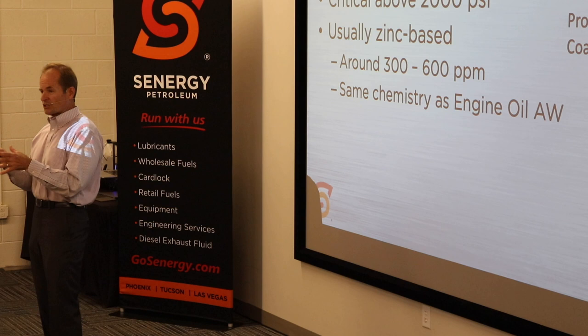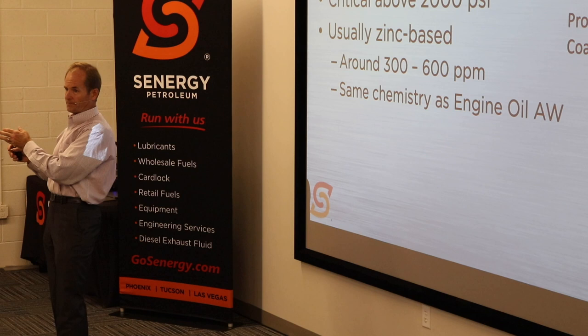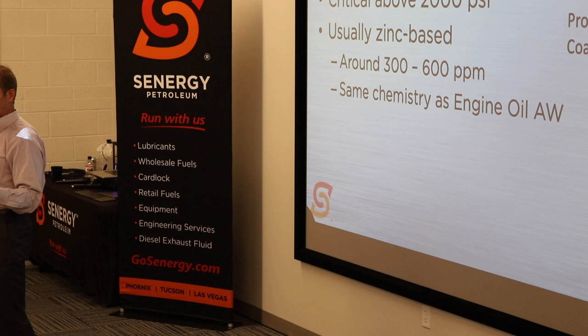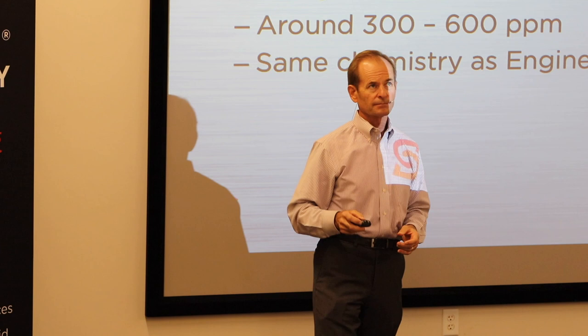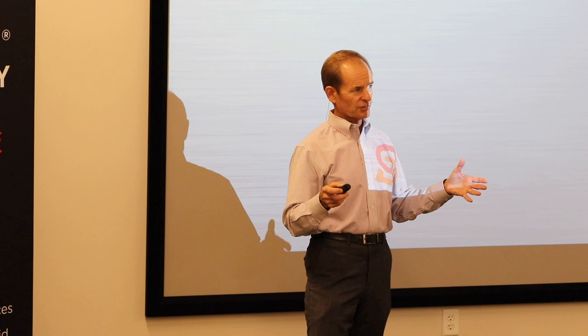The difference between engine oils and hydraulic oils: hydraulic oil runs 300 to 600 parts per million of this additive; passenger car motor oil might be around 750 parts per million; heavy-duty 15W40 maybe 1,200 parts per million. It's the same additive technology, but there's less of it in a mainstream anti-wear hydraulic oil — but it still does a good job. Most hydraulic oils with anti-wear will have that designation in the name as 'AW'; sometimes 'HD' or 'heavy duty' is part of it.